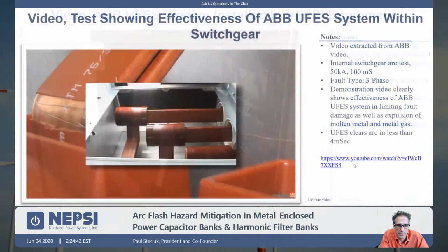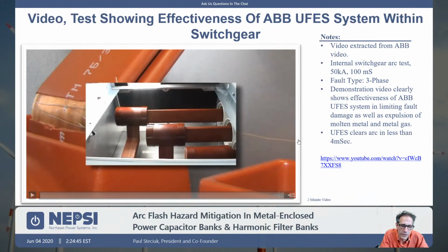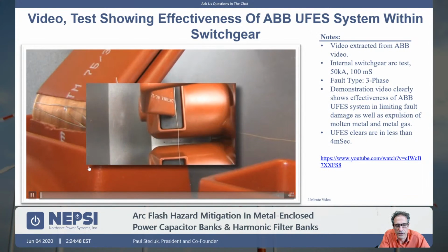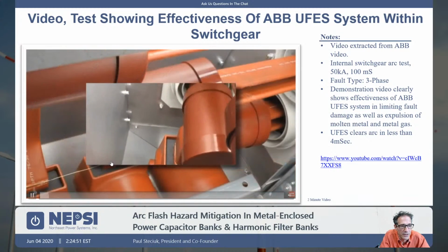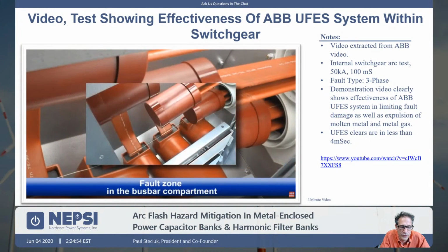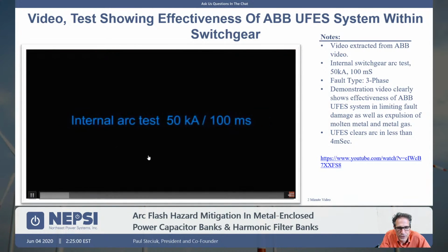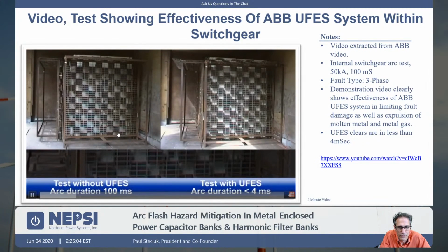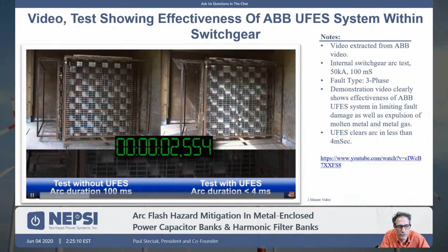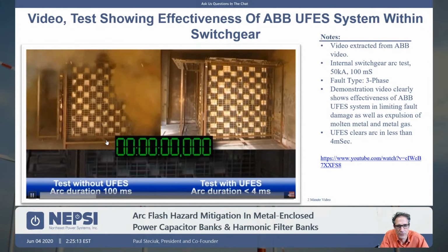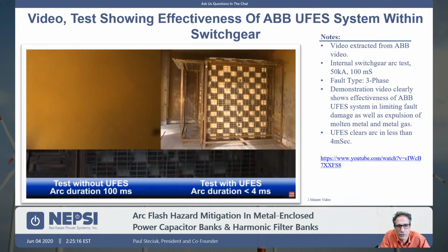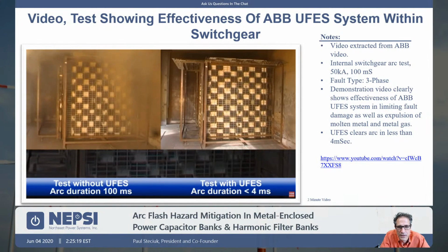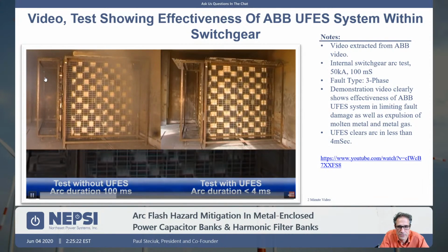so you can see how it actually works. And so here is another video, and this is an extract, and I will hit play on it. But this is the ultrafast earthing switch at a test laboratory. This is something that we've taken from ABB's website. What they've done is they shorted out bus bars within their switchgear, and they're applying an internal arcing fault. The one on the left is without the UFES system. The one on the right is with the UFES system. So as you see, this is the internal fault that was created with those wires. There's a significant amount of expulsion of gases. The one on the right, you barely saw anything.